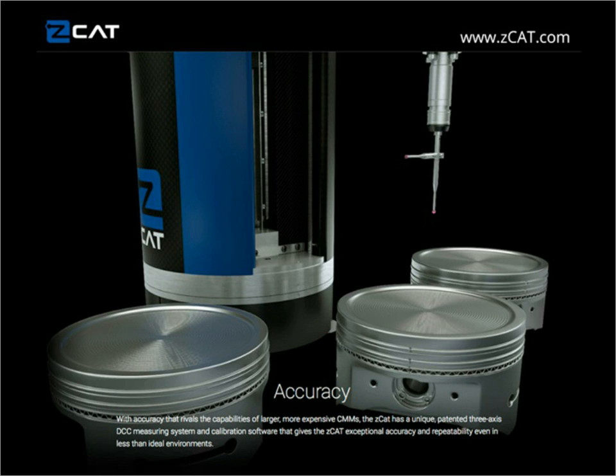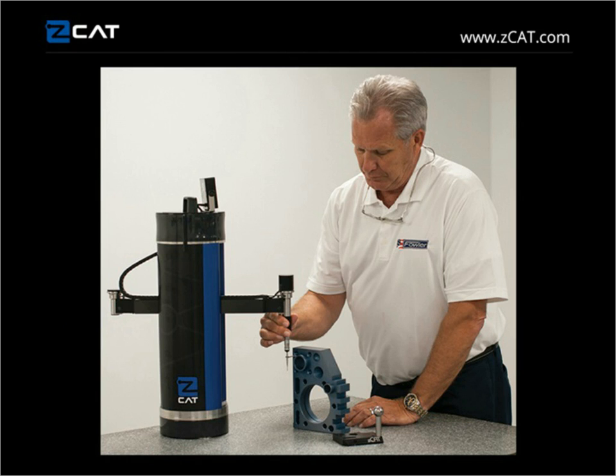Now, I mentioned before that the zCAT doesn't meet B89 spec. Therefore, very similar to what Homer experienced when he invented the Romer arm machine, it didn't meet B89 spec. Therefore, he had to create his own spec for the articulating arm machine, and we're doing the same thing with the zCAT. So what we're doing is we'll be simulating the B89 spec, and here you can kind of see how an operator would typically be using this.